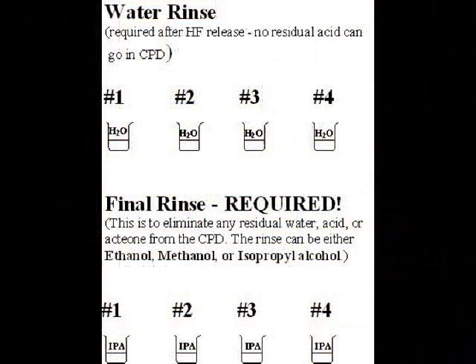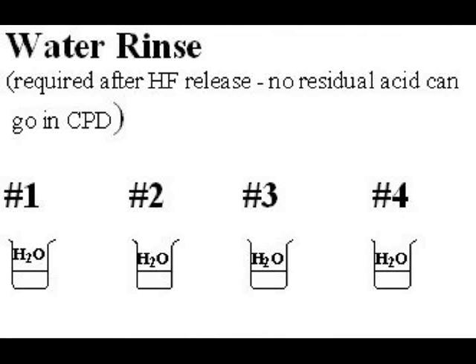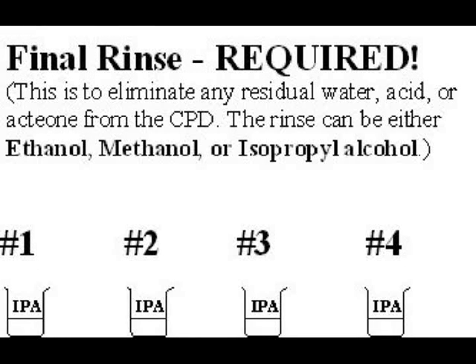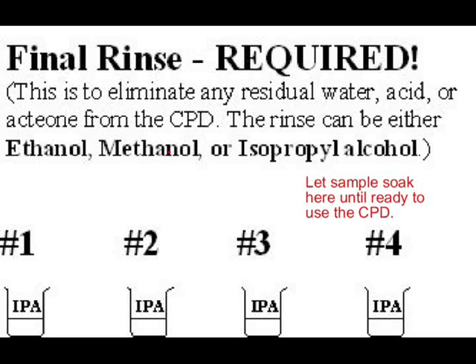The next step is preparing the samples with the following rinse steps. If a sample has been exposed to HF, it needs to be rinsed for several minutes in three to four different water baths. Each bath will remove any remaining residual HF. The sample then goes to the final rinse step before using the CPD. This last step eliminates any water from the sample. Rinse the sample for several minutes in three to four different solvent baths. The solvents allowed for this last step are ethanol, methanol, or isopropyl alcohol. If the samples have not been exposed to HF, they can skip the water rinse and go right to the final rinse. Leave the samples soaking in the last final rinse bath until ready to be placed in the CPD. Exposure to air should be minimized.